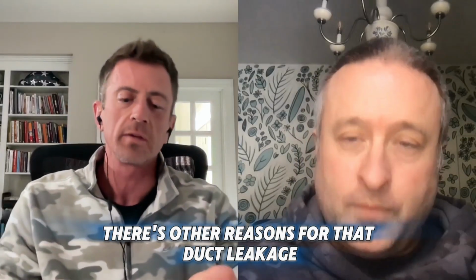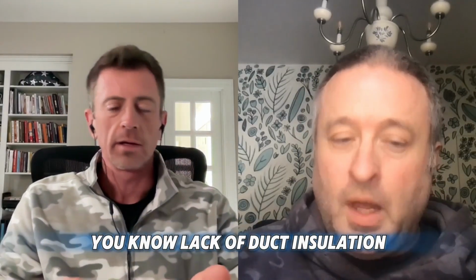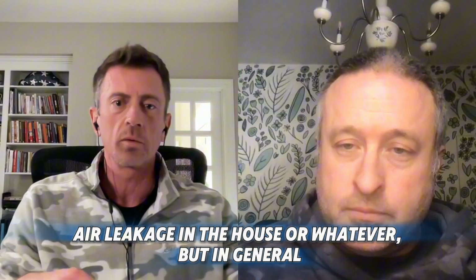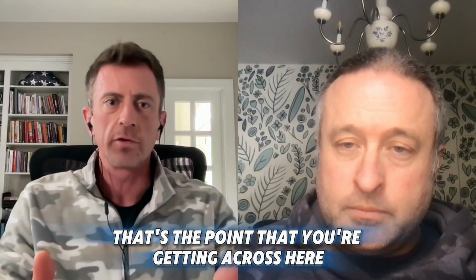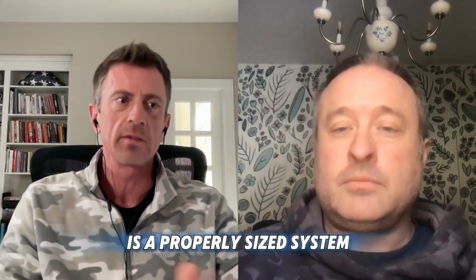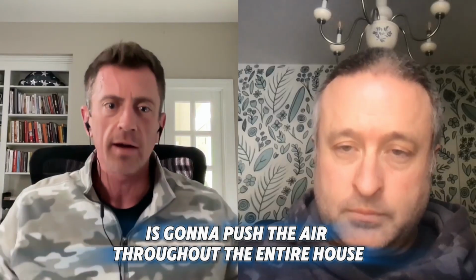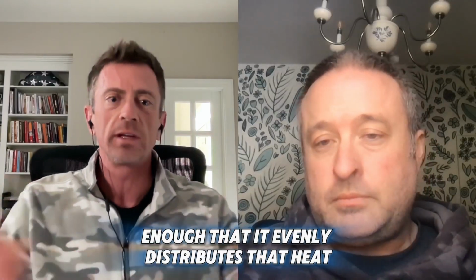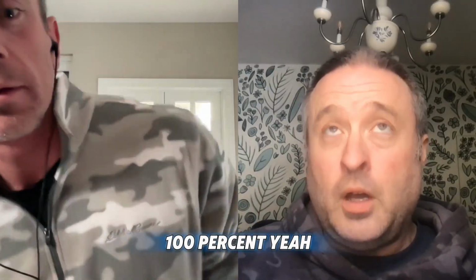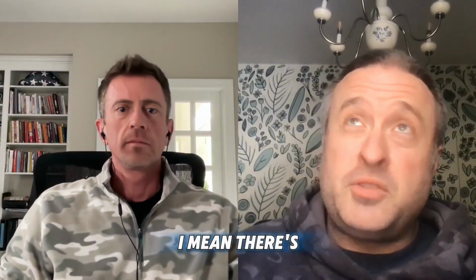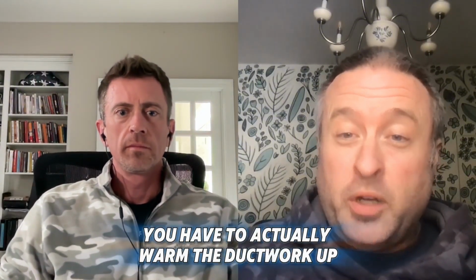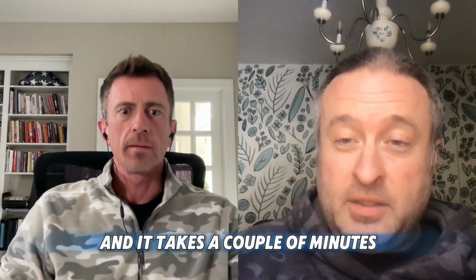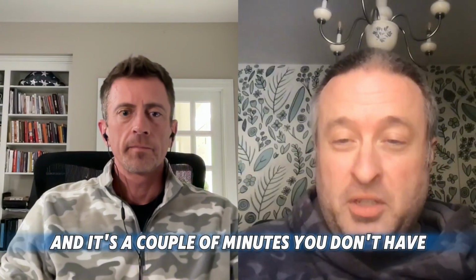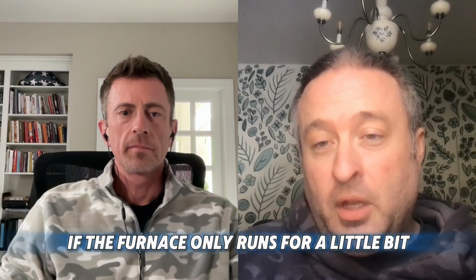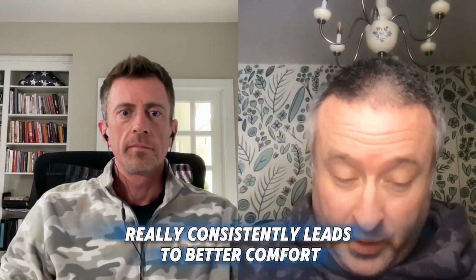And there are other reasons for that: duct leakage, lack of duct insulation, air leakage in the house or whatever. But in general, that's the point you're getting across here: a properly sized system is going to push the air throughout the entire house enough that it evenly distributes that heat or cold. 100%. Yeah. The other piece there is you have to actually warm the ductwork up going to the other side of the house. Yeah. And it takes a couple of minutes, a couple of minutes you don't have if the furnace only runs for a little bit. So downsizing the system really consistently leads to better comfort.